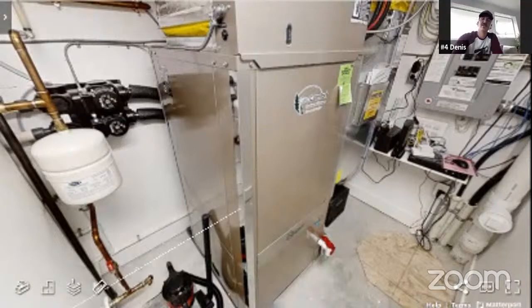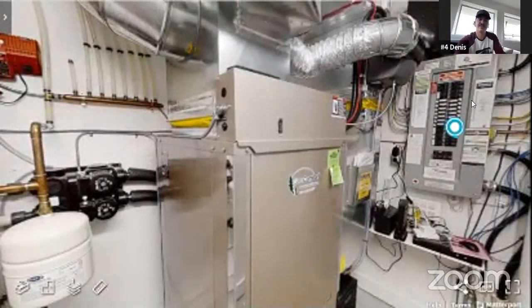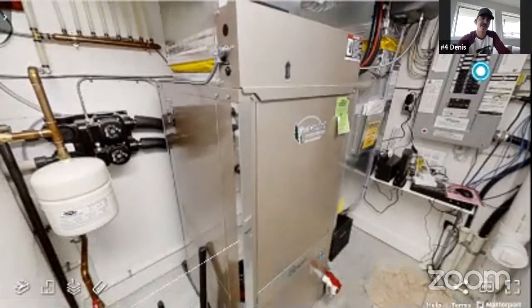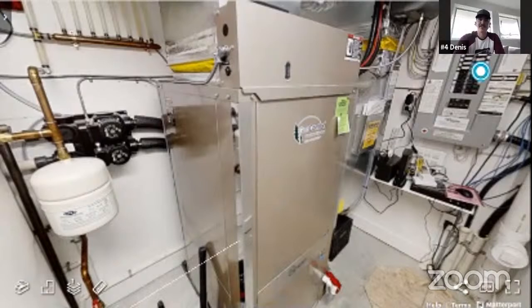Yep, absolutely. But instead of having a burner section that burns a bunch of fuel, all it has is the air conditioning coil, which during the heating season, there's a reversing valve because it's a heat pump, which takes the charged gas and the heat of compression and then dumps that into the house. And so you hear a click and suddenly you're doing air conditioning. Yeah, you hear a click, hiss, because the refrigerant is changing directions, and then you have air conditioning.